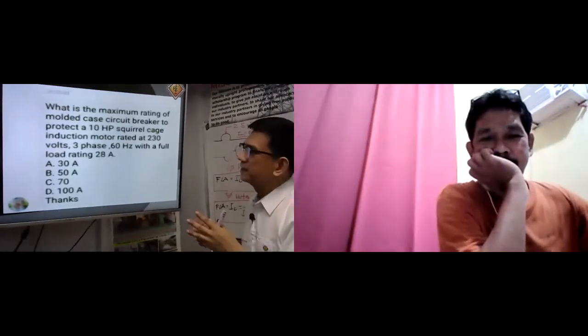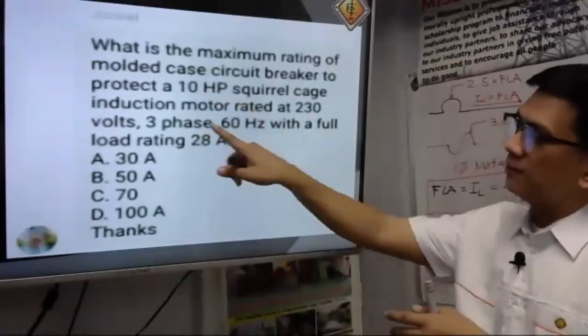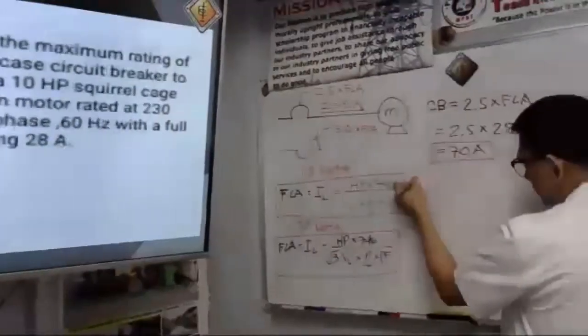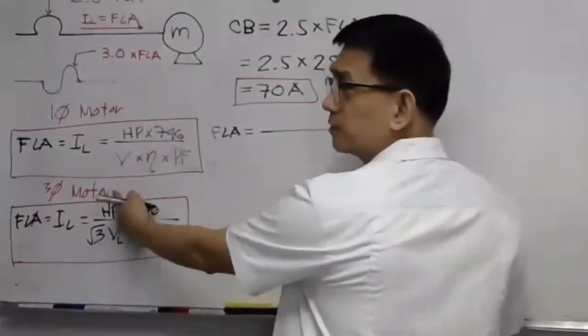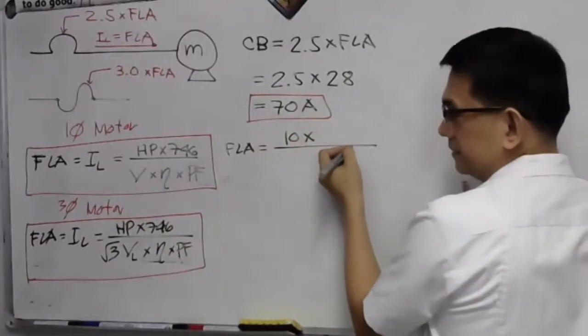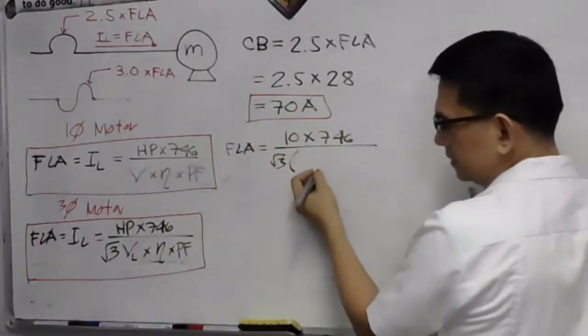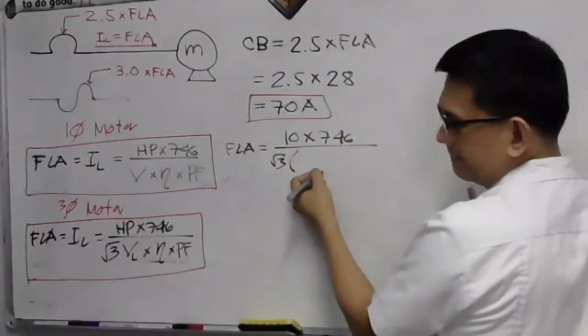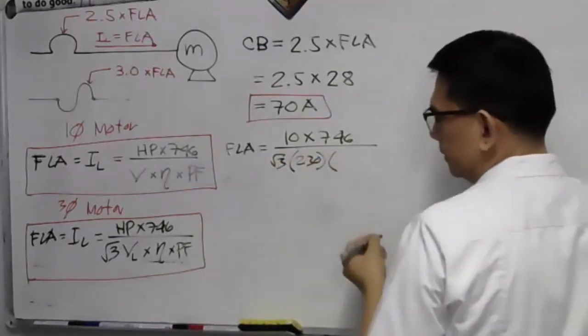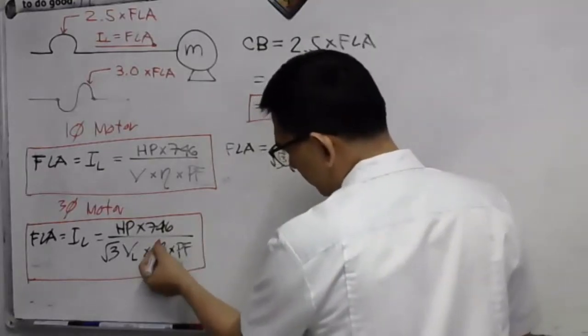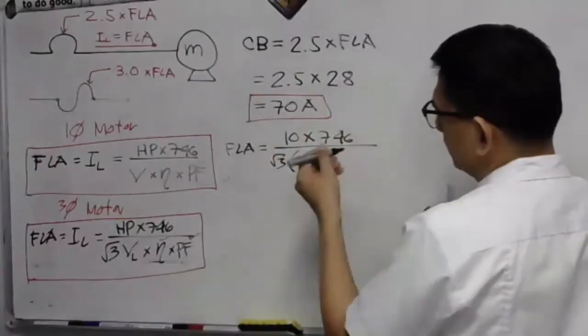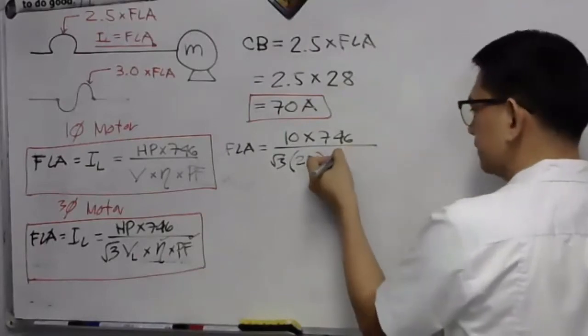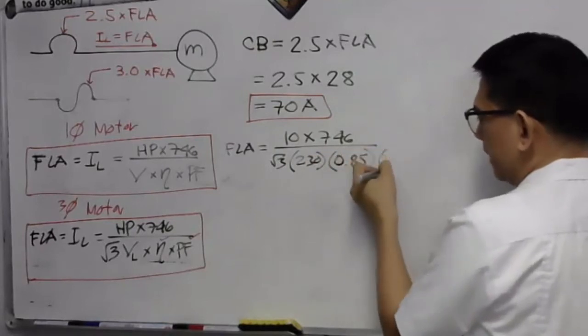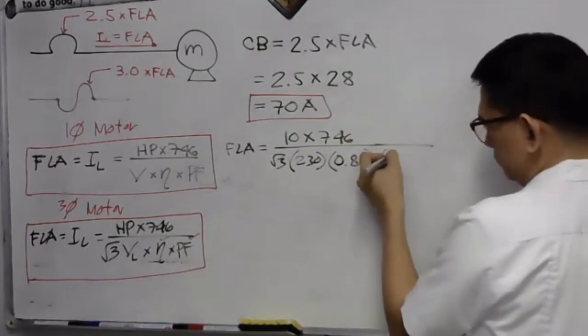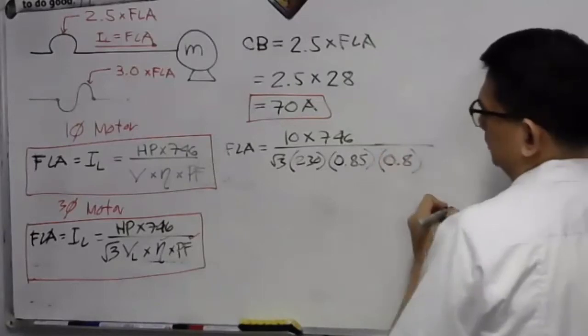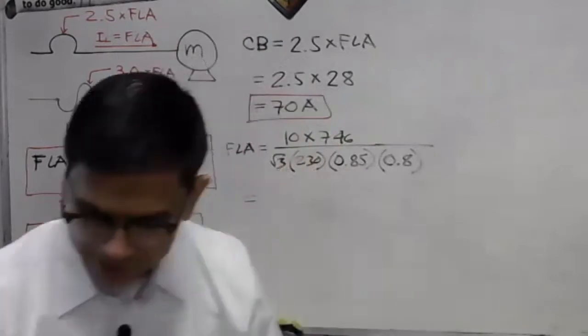Just in case you have a 10 horsepower, 230 volts, 3-phase motor, I will calculate the full load ampere. According to the 3-phase formula, we have 10 times 746, divided by square root of 3, and the voltage is 230 volts. I will just assume the efficiency and power factor. Let's say our efficiency is 85%, meaning 0.85, and our power factor is 0.8. So let's see what the full load ampere is.